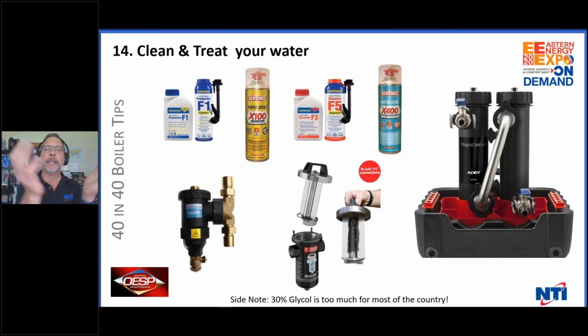All this product does is take all that stuff that's laying out in the pipes and gets it into solution. Makes it all murky. Makes it look like low tide. All that crap's in the water. And then you flush it out within 14 days. Think of this. You take your material takeoff, and while you're doing that, put in your cleaner and let the circulators run. Then when your guys come to install, flush it out.